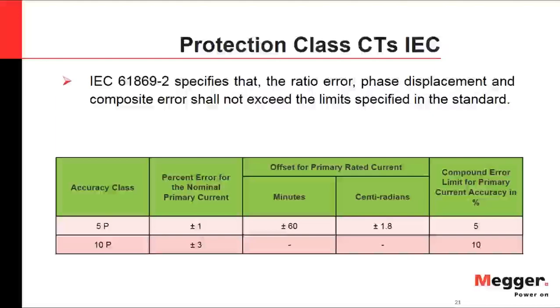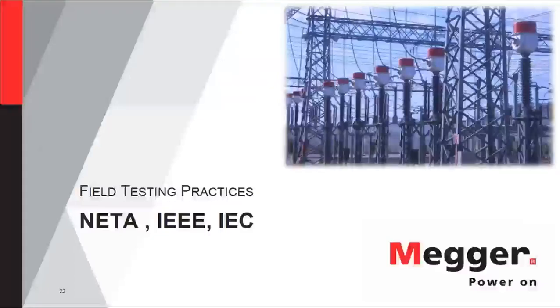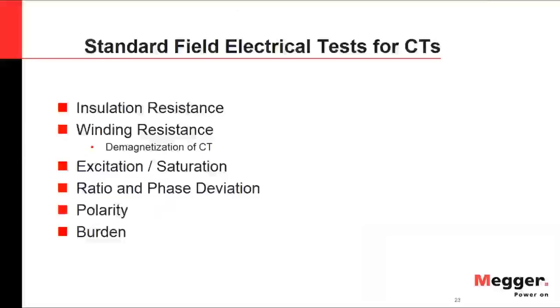Let's discuss field testing practices according to reference standards like NETA, IEEE, and IEC. In summary, when going to the field we are required to perform: insulation resistance test, winding resistance test, excitation or saturation test, ratio and phase deviation test, polarity test, and burden test. We also need to account for demagnetization of the CT after the winding resistance test.